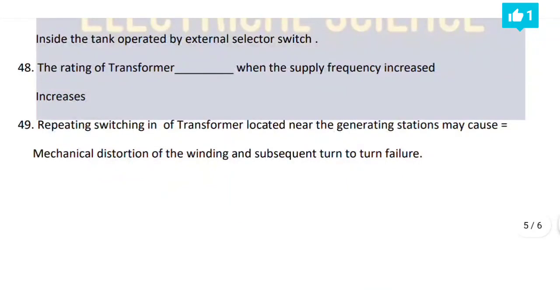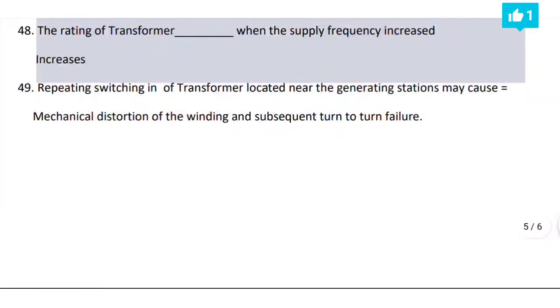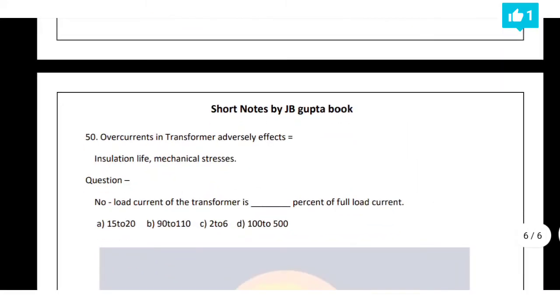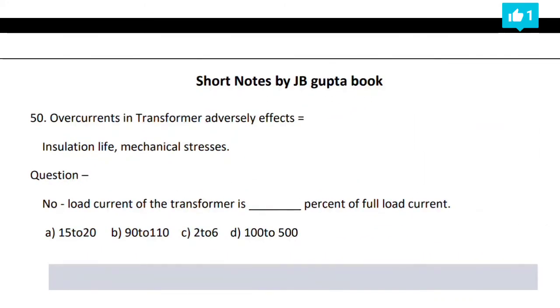49th point, repeated switching in of a transformer located near the generating station may cause mechanical distortion of the winding and subsequent turn to turn failure. So our last point, overcurrent in a transformer adversely affects insulation life and causes mechanical stresses.